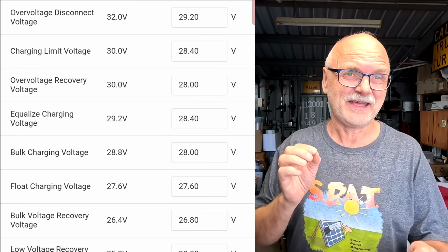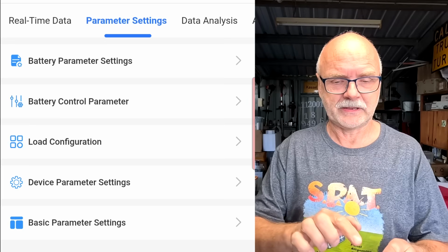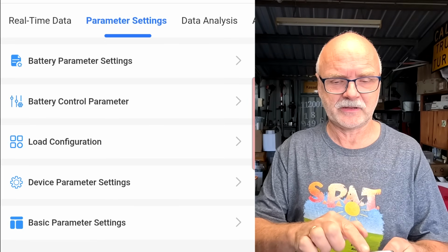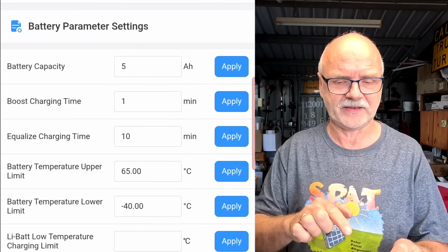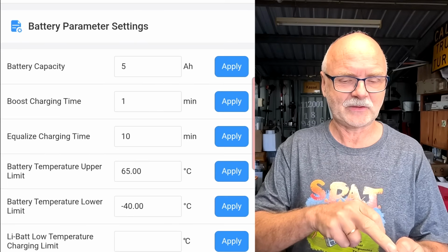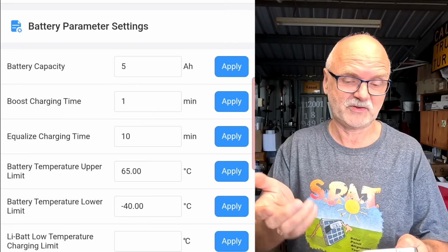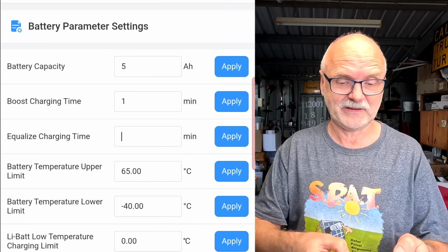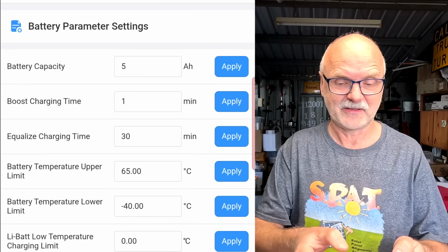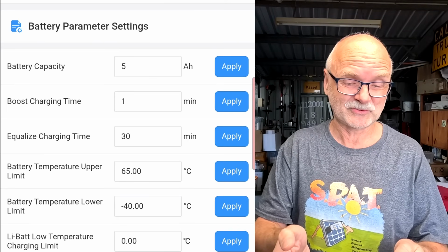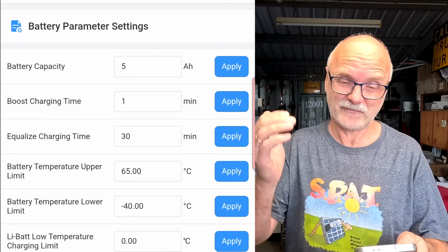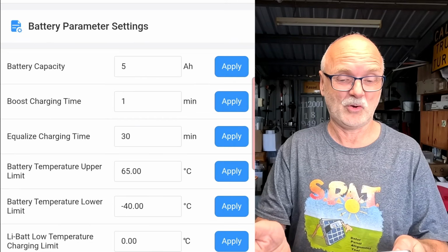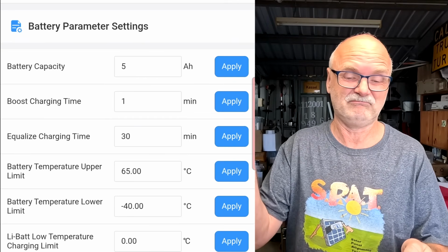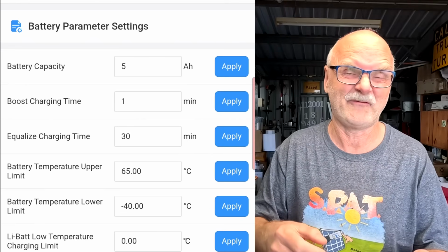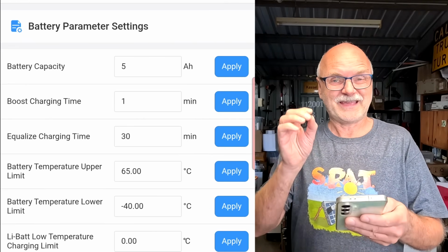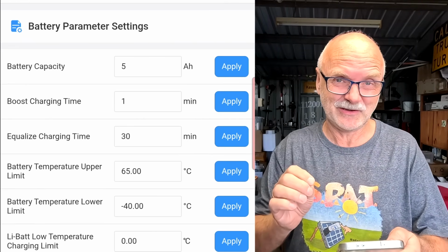There's something under battery parameter settings where we can set an equalization charge time, currently 10 minutes. I'd probably set this to 30 minutes. This up here is our absorption timer, which I've set to 1 minute only for testing purposes, but later this will also sit at maybe half an hour or so. We can set the timers here individually as well.